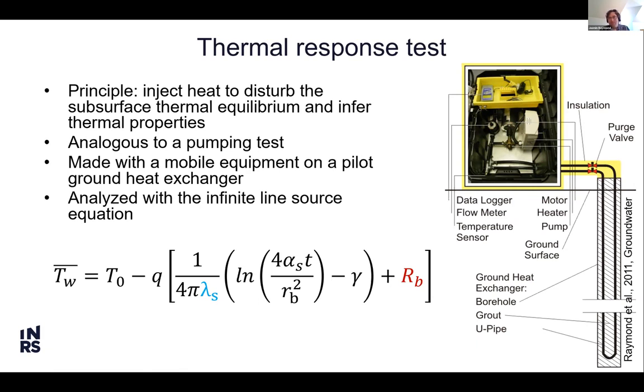And it will depend on the heating and cooling need of the building. But to design the system, we'll just use an electric water heater to heat the water, circulate it with a pump, measure the flow rate with a flow meter, and measure the temperature at the inlet and outlet of the ground heat exchangers, and basically evaluate the temperature response. We inject heat in the ground, disturbing the thermal equilibrium of the subsurface to infer the thermal conductivity.